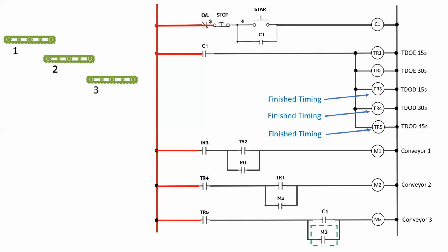By using 5 time delay relays, we can orient the sequence of operation for a 3-motor conveyor belt system so that the order of start is opposite from the order of stop.